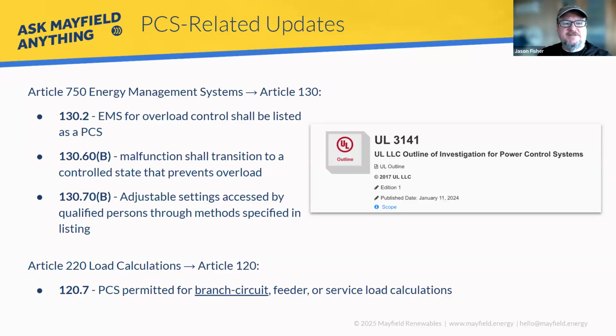That's a perfect example of where now, if you can add PCS to one or both of them, or to the panel board that's making the interconnection, then you can actually enforce a practical current limit, right? Not just have to take the two nameplates and say what is the maximum continuous current output, and use those. So that's a big one.